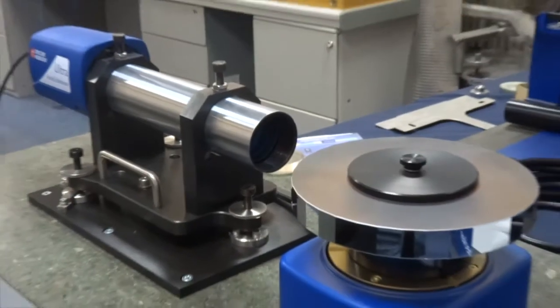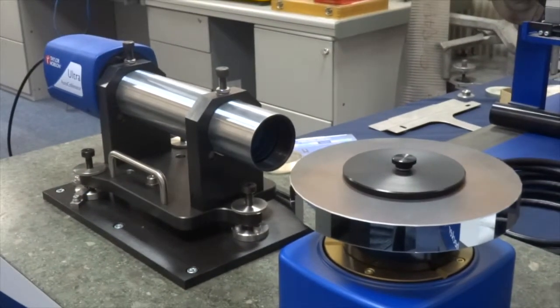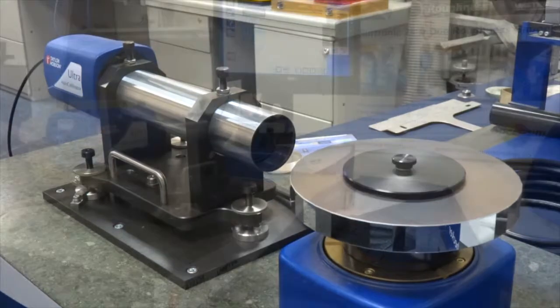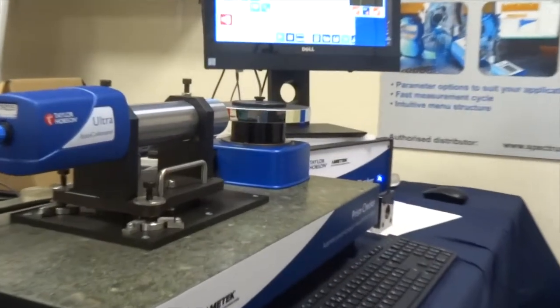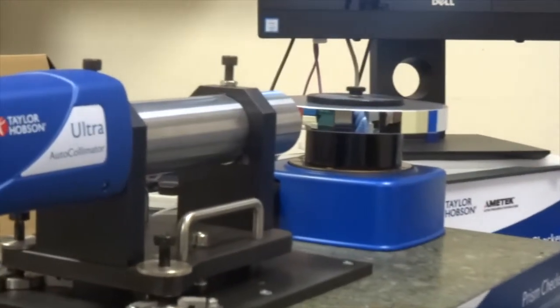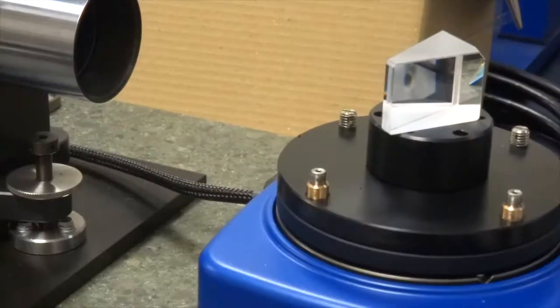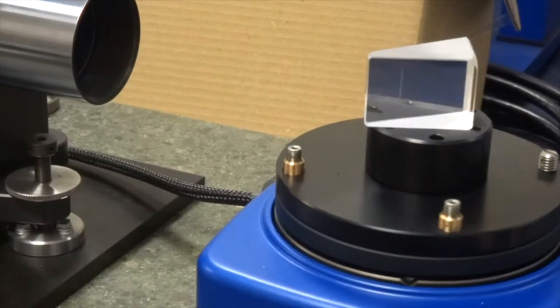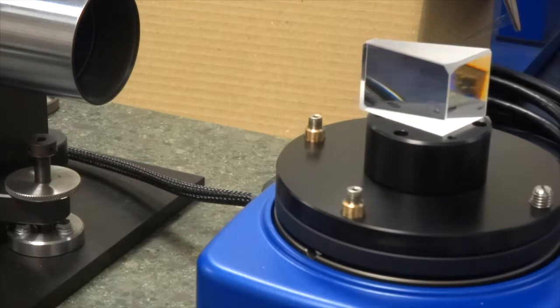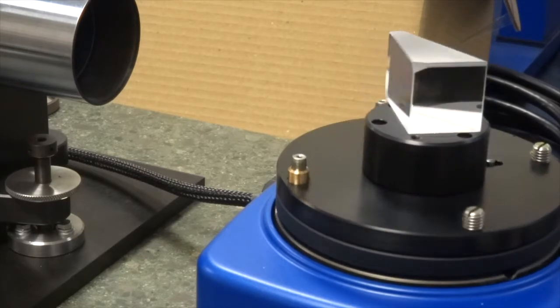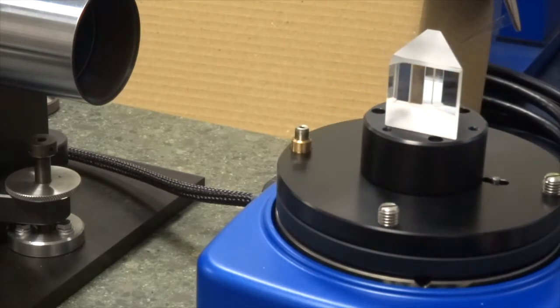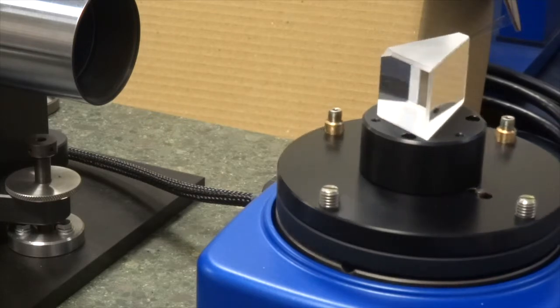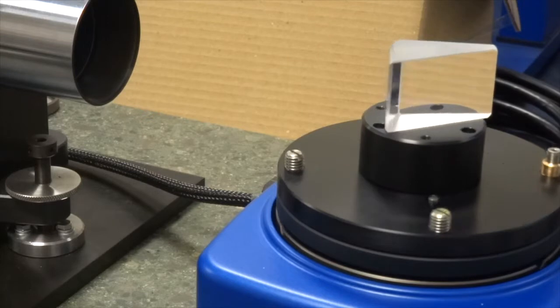The system combines two great names with the Taylor Hobson Ultra Autocollimator and the Aerotech Rotary Stage. The Ultra Autocollimator uses the latest CCD camera technology to produce 0.2 seconds accuracy in both the X and Y axis, and also offers a wide measurement range.